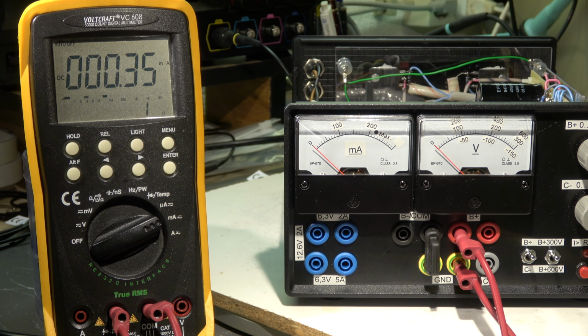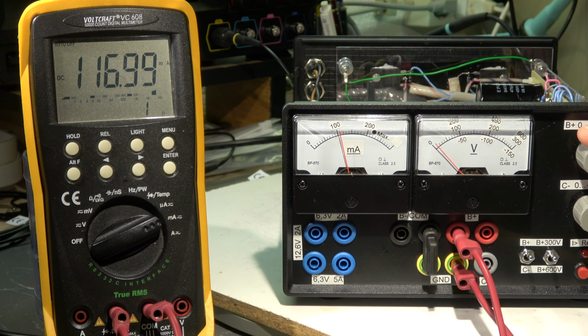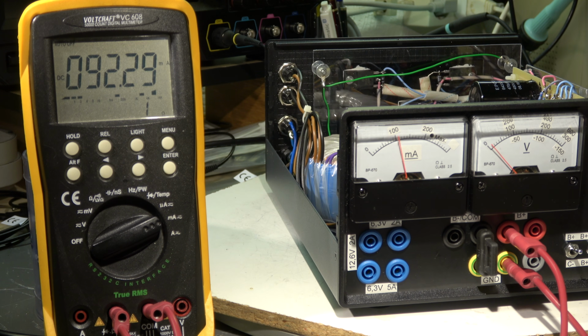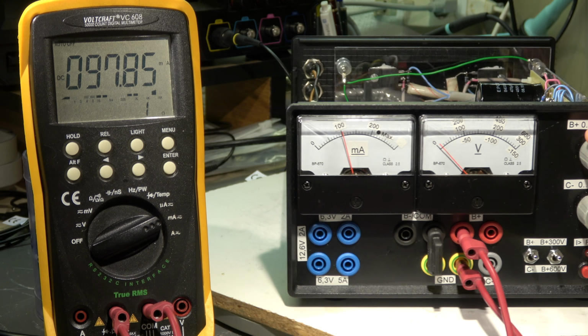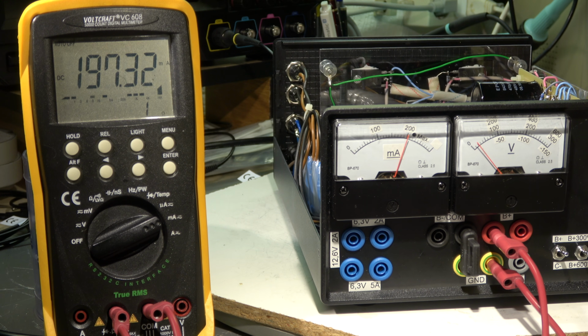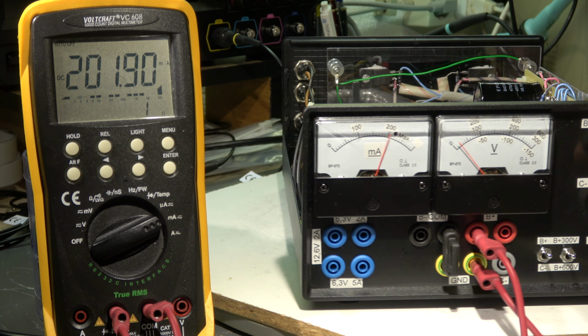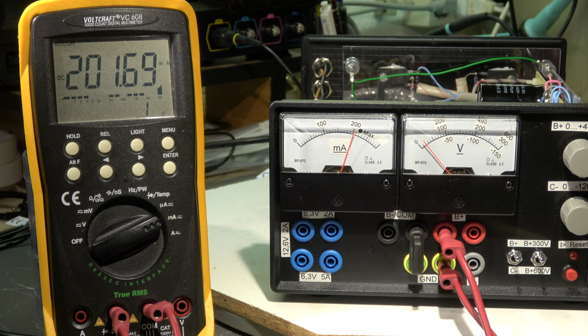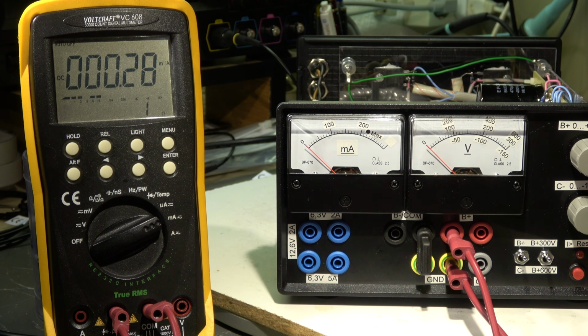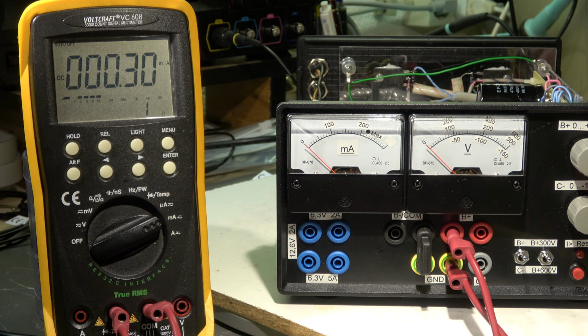Okay, works also. Calibration seems to be okay. 100 milliamps. Could improve it a little bit. 202, it's okay. It is not necessary, because these instruments are not very precise. They have specified class 2.5. So this is not a precision instrument. It only costs some euros per unit. It's not worth discussing it. If you need more accurate metering, use external digital multimeters.